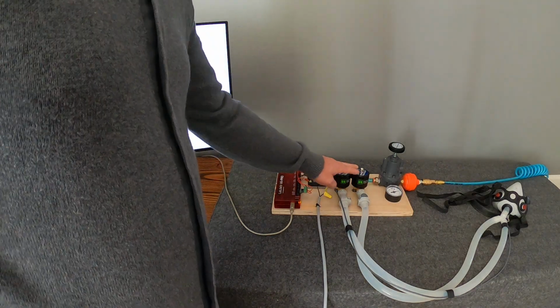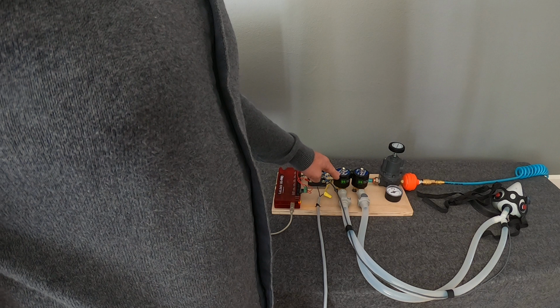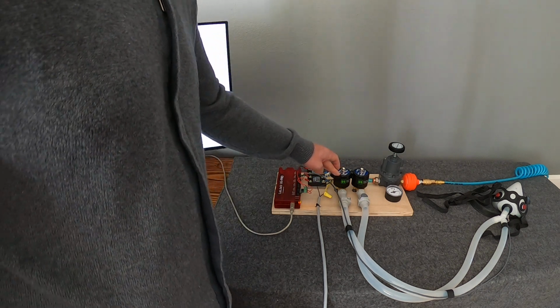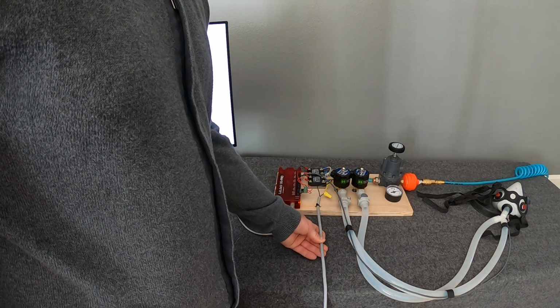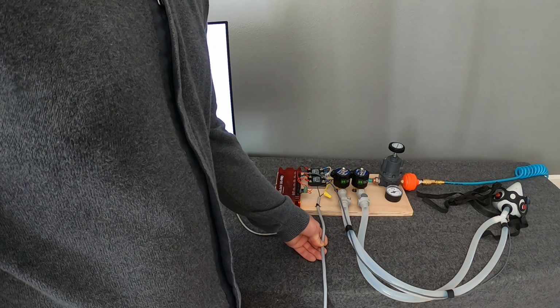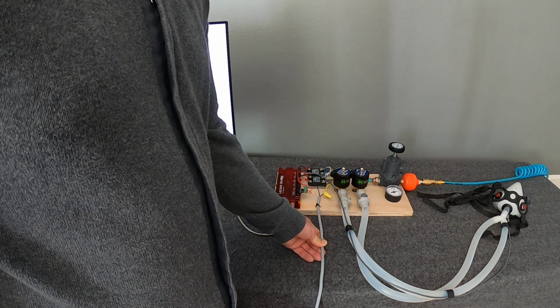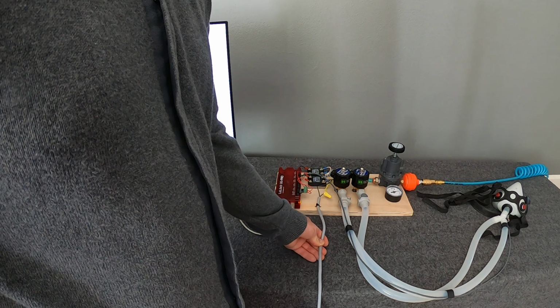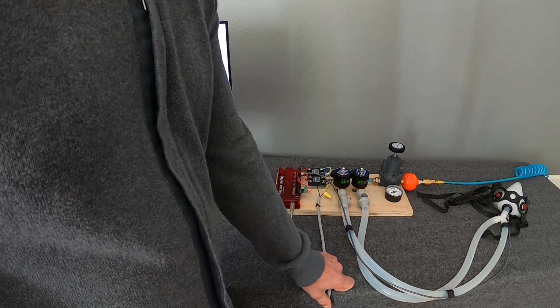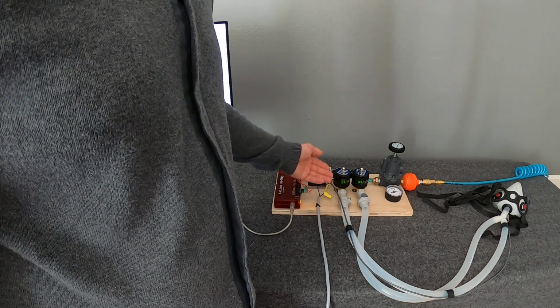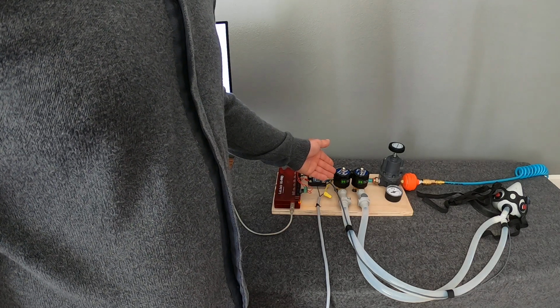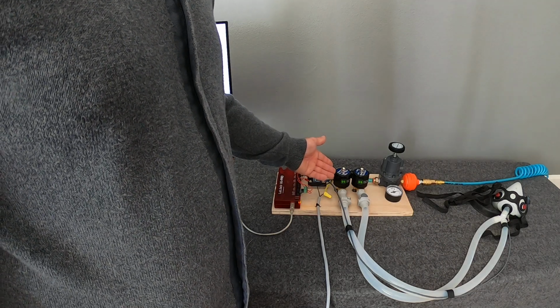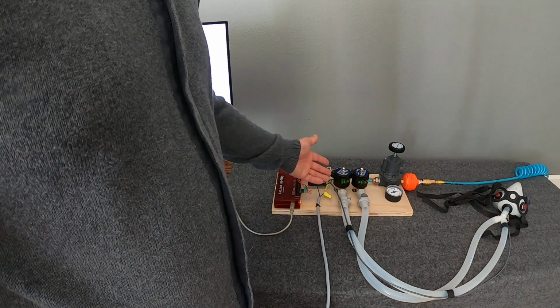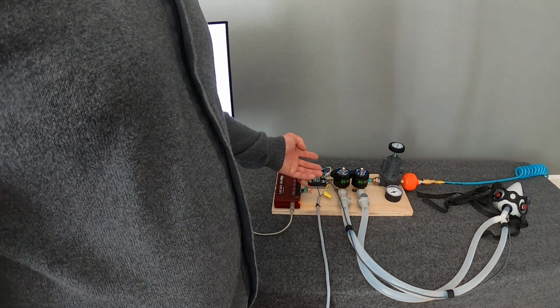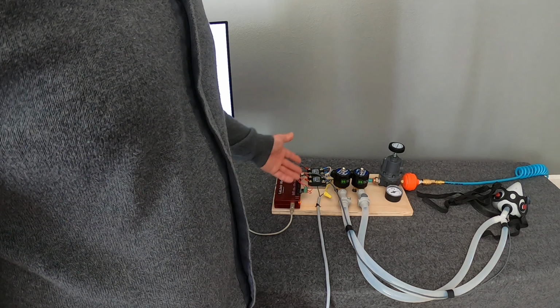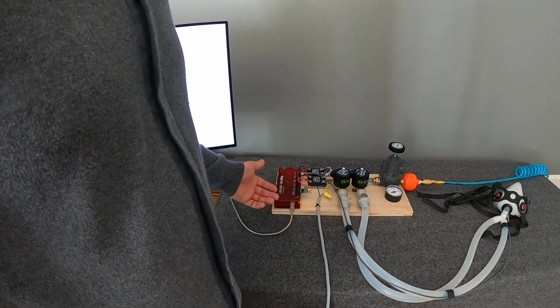The solenoid valves have solenoid coils that operate on 120 volts AC. The 120 volt power comes through this cord that's just plugged into a standard wall receptacle. 120 volts AC is standard house power supply here in the United States, so that's what that's plugged into. Solenoid coils that work off DC, AC, or various voltages, whatever you really have access to, could alternately be employed. However, the electronics that control them may be slightly different.